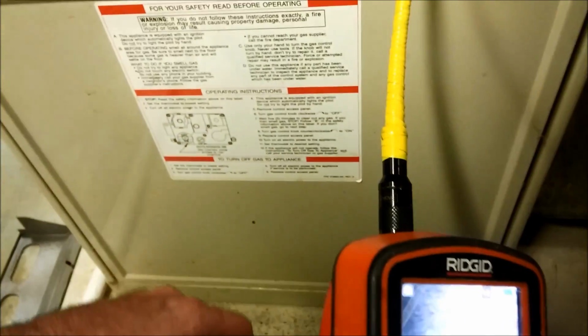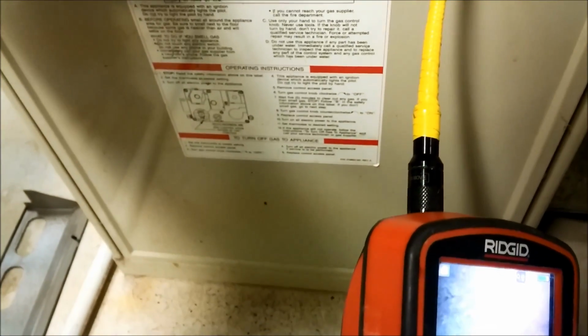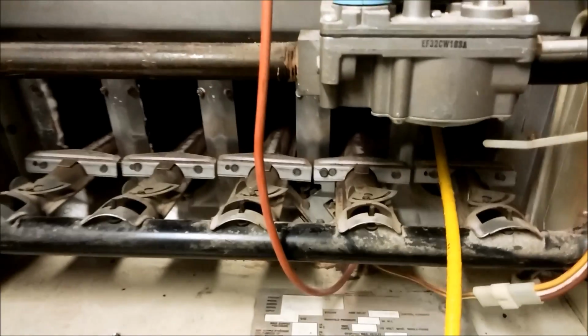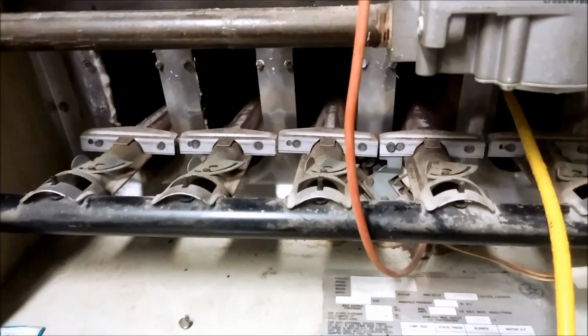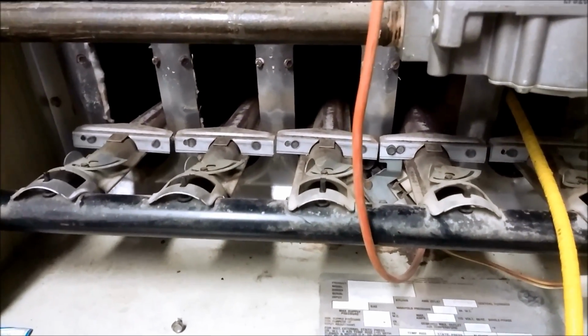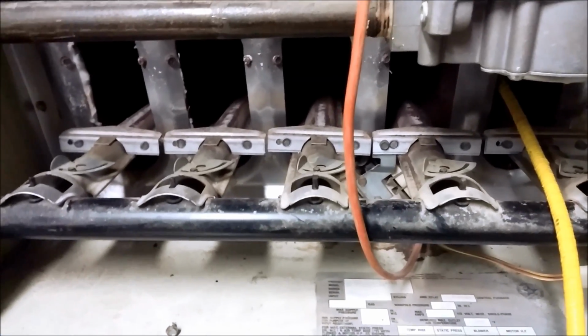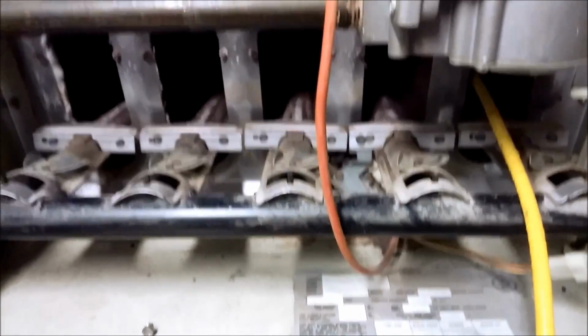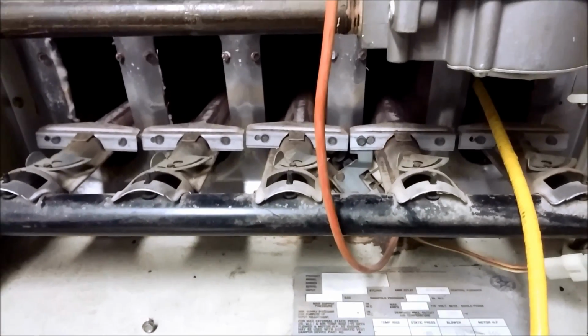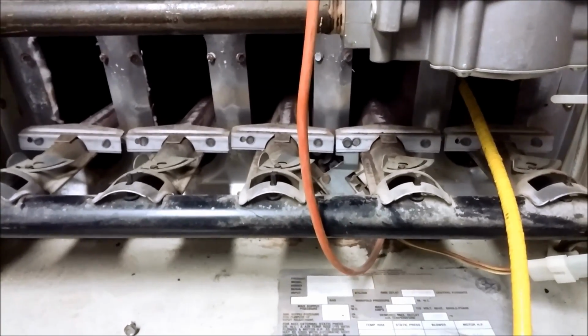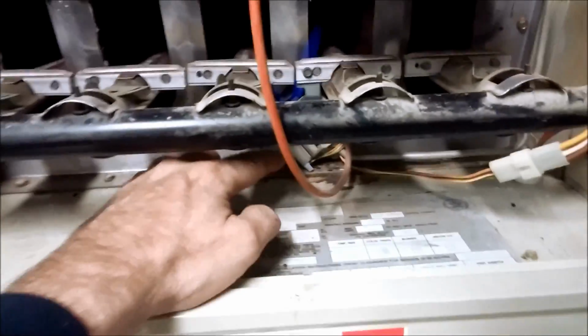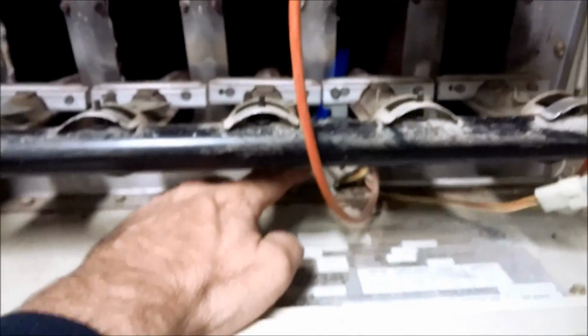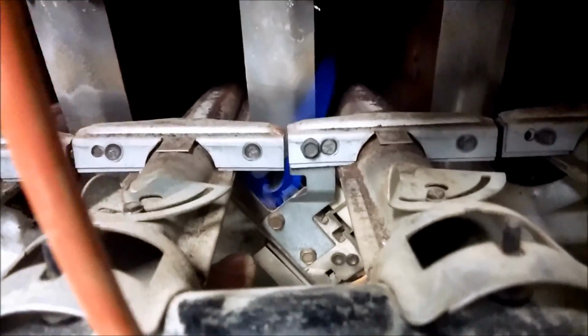You know, one thing I want you guys to see. Let me start this thing up. This thing is cracked up bad. I want you to see if there's any flame impingement or flame rollout. Hold on a second. Okay, we're going to light it up. It's a 3-wire pilot system with bimetal pilot burner.